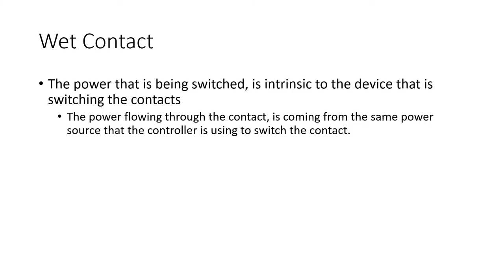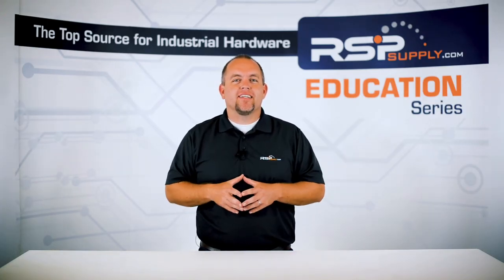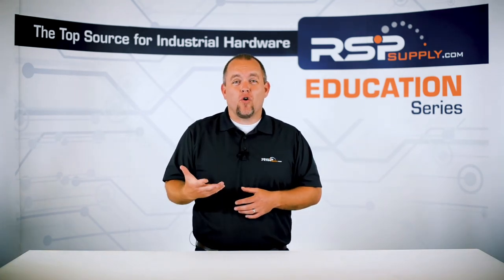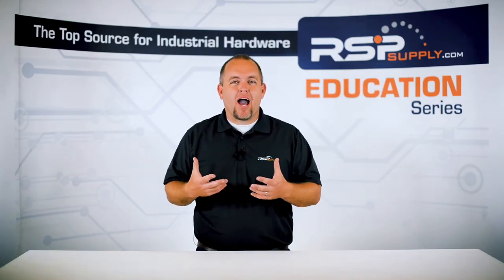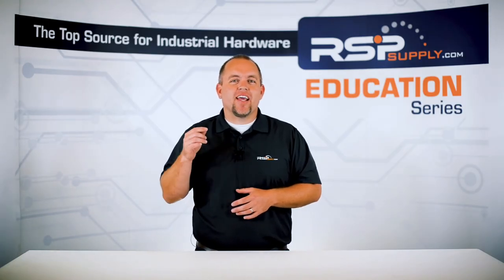Now let's talk about a wet contact. Wet contacts are different in one main area: the power that is being switched is intrinsic to the device that is switching the contacts. In other words, the power flowing through the contacts is coming from the same power source that the controller is using to switch the contact. For example, a common device we are all familiar with is a furnace in our homes. This furnace is most likely being supplied 120 volts or 240 volts AC power from our home's electrical panel.